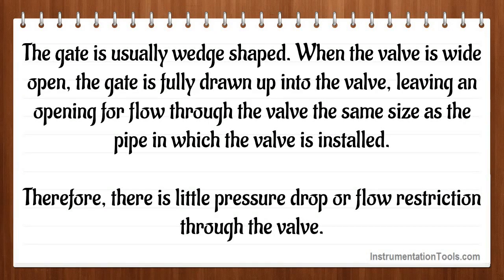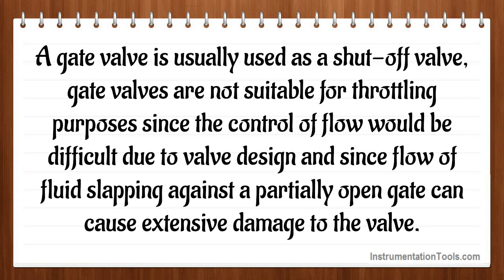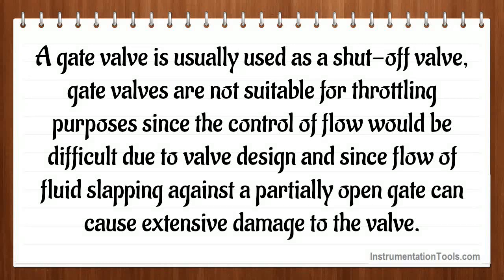The gate is usually wedge-shaped. When the valve is wide open, the gate is fully drawn up into the valve, leaving an opening for flow through the valve the same size as the pipe in which the valve is installed. Therefore, there is little pressure drop or flow restriction through the valve. A gate valve is usually used as a shut-off valve. Gate valves are not suitable for throttling purposes since the control of flow would be difficult due to valve design and since flow of fluid slapping against a partially open gate can cause extensive damage to the valve.